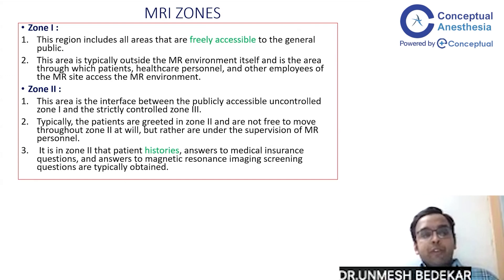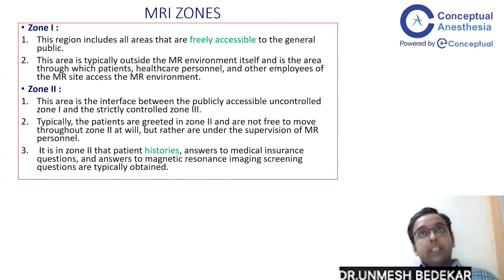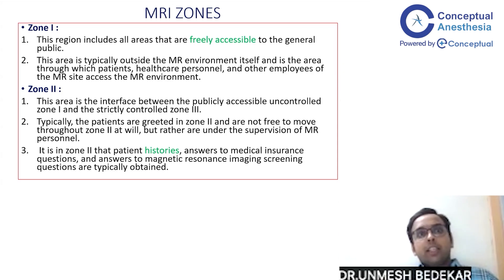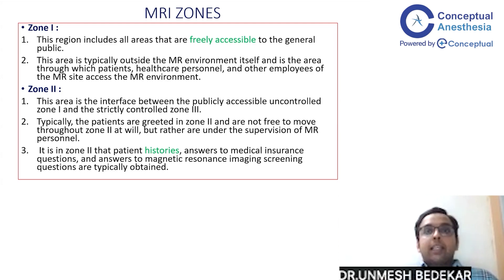Typically an MRI suite — as you may have noticed in your hospital — is situated on the ground floor. We will discuss why later. The MRI suite is divided into four zones for safety purposes. Zone 1 is the region that includes all areas freely accessible to the general public, outside the MR environment itself, through which patients, healthcare personnel, and other employees access the MR environment.